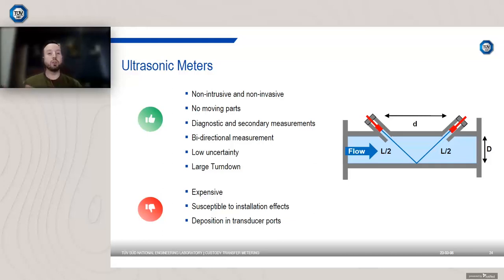They don't have any moving parts, so they're less susceptible to mechanical damage. They can give you diagnostic and secondary measurements. So ultrasonic meters can now tell you things about the profile of your flow. Have you got swirl within the flow stream? The speed of the propagation of the ultrasound is dependent on things like the composition of the fluid. So some can now indicate things like the density of the fluid.